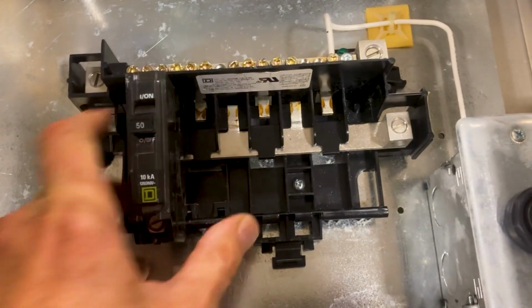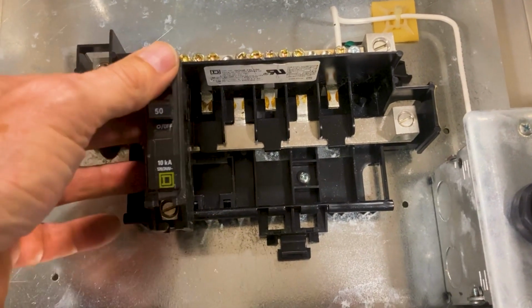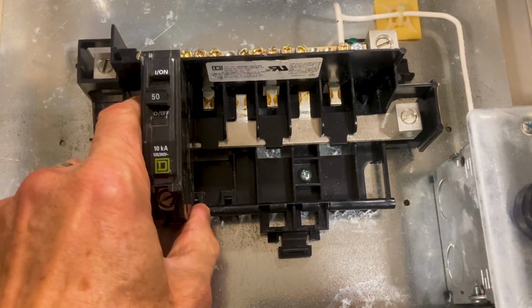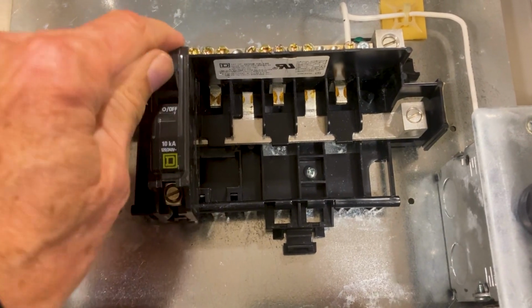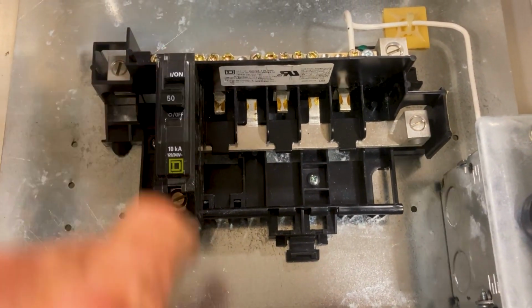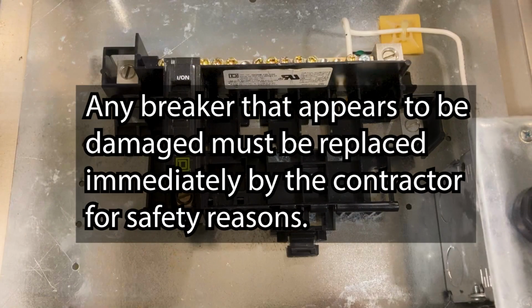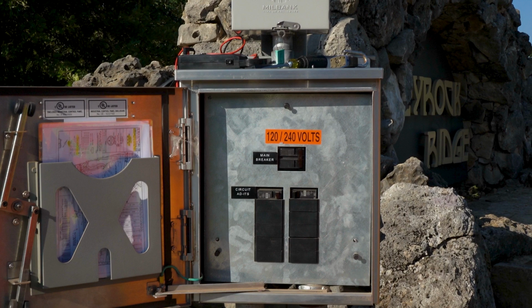Plug-in stab lock type breakers are sometimes incorrectly installed. If they are not fully connected to the bus bars, they will not operate properly. Any breaker with a part that is found to be broken, cracked, or showing signs of overheating must be replaced by the contractor immediately. Each breaker must be marked with the load served. To comply with this requirement, a circuit directory is required to be correctly filled in.